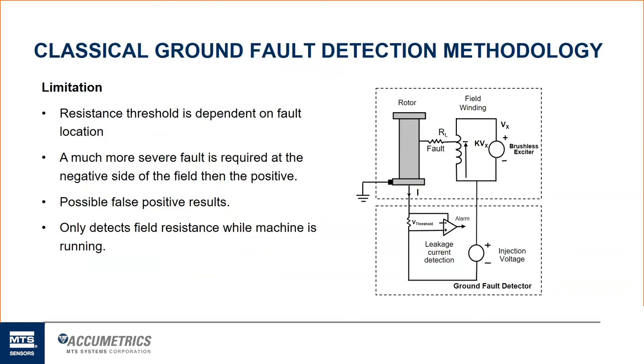So a good field, when it's rebuilt, rewound, and first goes into service, may be many tens of megaohms. Most utilities are only concerned with values below 500K. It's very difficult to measure any accurate resistances over 500K ohms. It just looks like a massive open wire at that point. And as long as it's very high like that, utilities aren't concerned. They're concerned with low values of resistance.